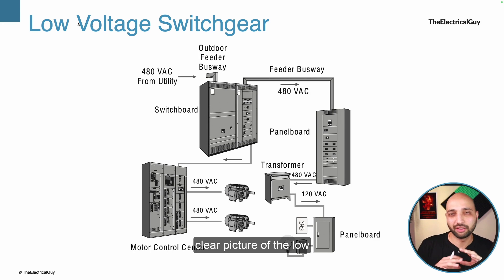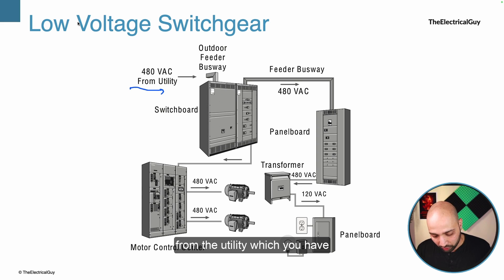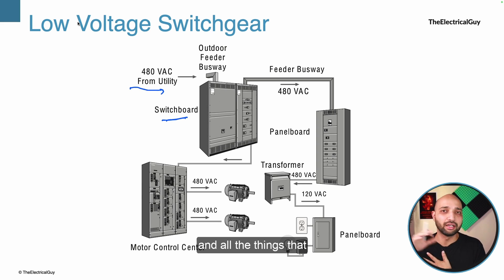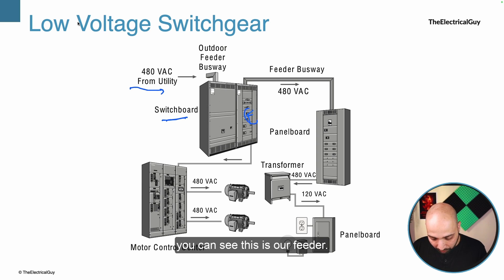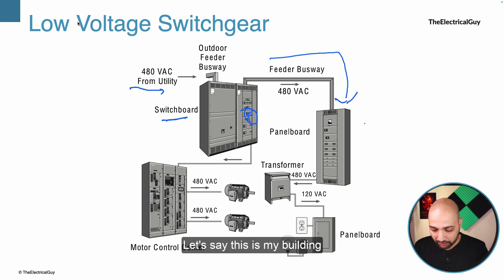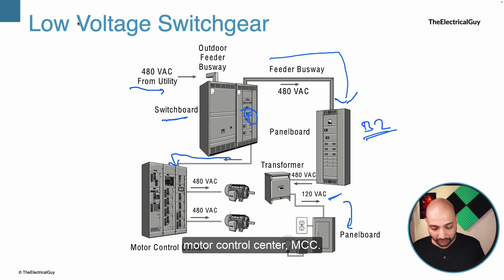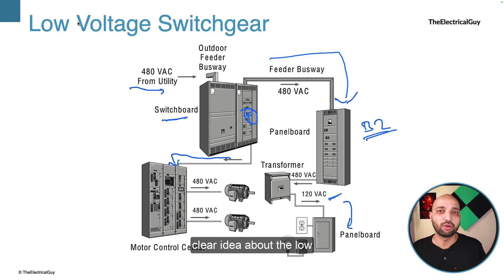This image gives a clear picture of the low voltage switchgear. The incoming supply from the utility is connected to the switchboard, called the incomer, which contains air circuit breakers, control circuitry, relays, CTs, VTs, and all the components discussed. A feeder from the incomer supplies two different loads: one via a feeder busway to a building B2 panel, which steps down to 120V AC for the flats, and another to the Motor Control Center (MCC) that controls all the building's motors.